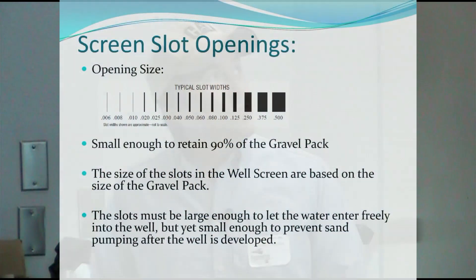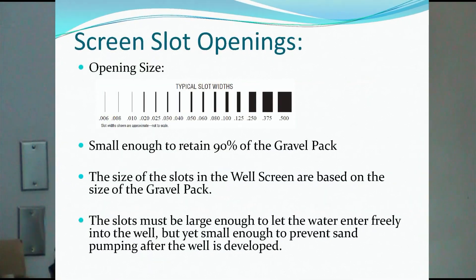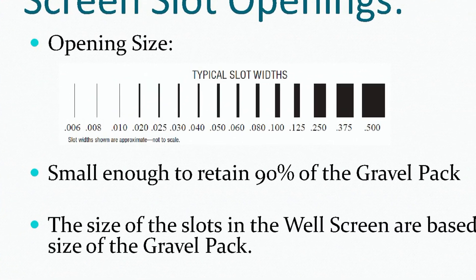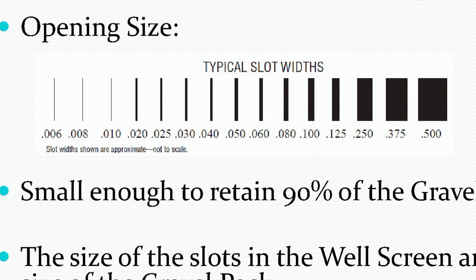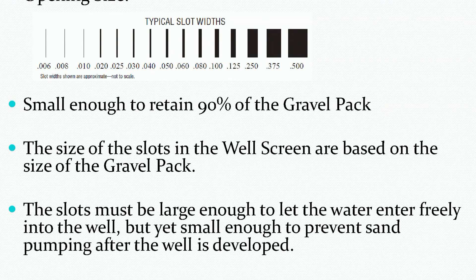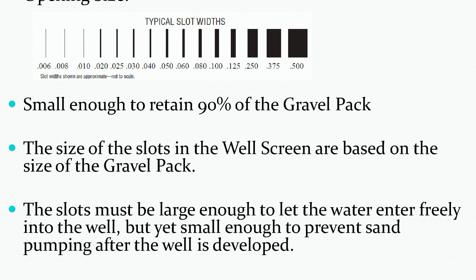For the screen slot opening, there's a whole range of sizes. The opening should be small enough to retain the gravel pack — the size of the slots is based on the size of the gravel pack. The slots must be large enough to let water flow freely into the well, but small enough to prevent sand from coming in.